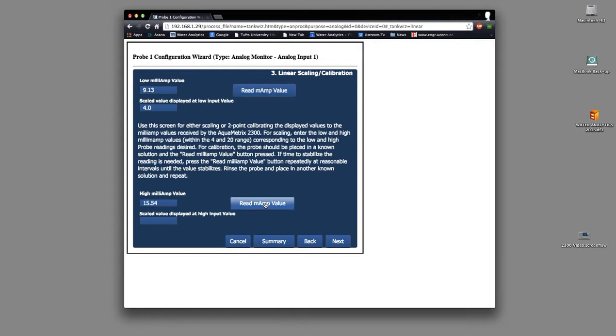As you can see, it's still going up. As I wait for it to settle down, I'll enter the value of pH 10. Let's make sure the probe reading has settled down. Let's pretend it has. Typically, this will take about 30 seconds to a minute to be sure.